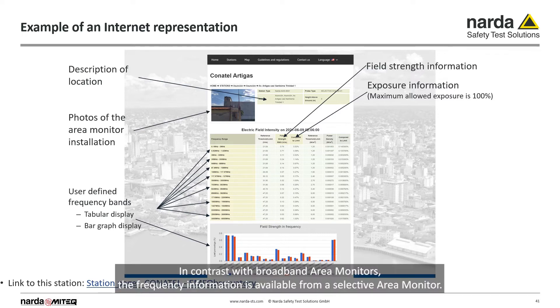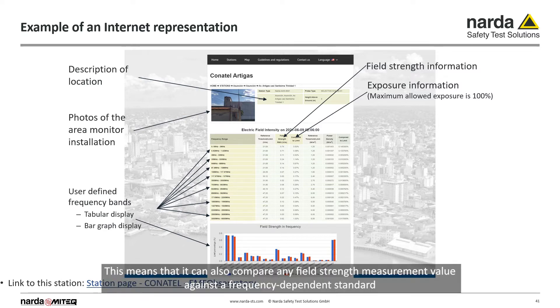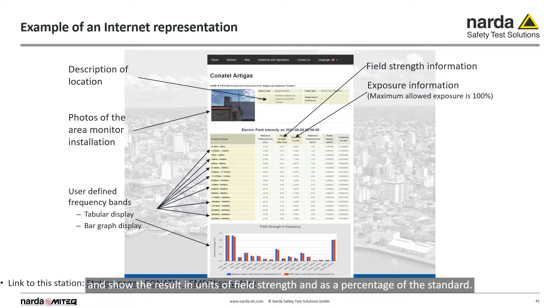In contrast with broadband area monitors, the frequency information is available from a Selective Area Monitor. This means it can also compare any field strength measurement value against a frequency-dependent standard and show the result in units of field strength and as a percentage of the standard.